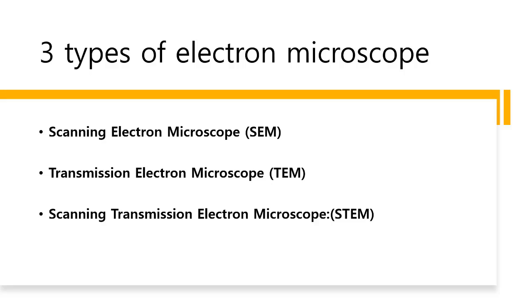Now, electron microscopes work by using an electron beam instead of visible light and an electron detector instead of our eyes. An electron beam allows us to see at very small scales because electrons can also behave as light. They have the properties of a wave with a wavelength that is much smaller than visible light, a few trillionths of a meter. With this wavelength, we can distinguish features down to a fraction of a nanometer. Let's explore the different types of electron microscopes, how they work, and some of their applications.